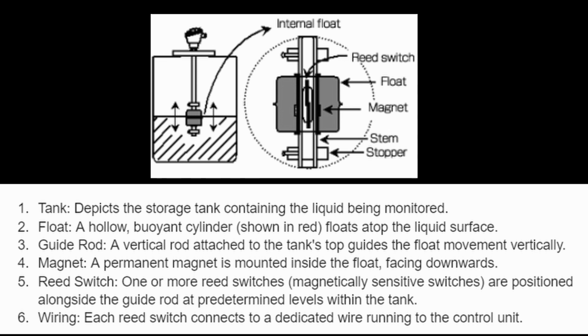1. Tank depicts the storage tank containing the liquid being monitored. 2. Float. A hollow, buoyant cylinder, shown in red, floats atop the liquid surface. 3. Guide rod. A vertical rod attached to the tank's top guides the float movement vertically. 4. Magnet. A permanent magnet is mounted inside the float, facing downwards.